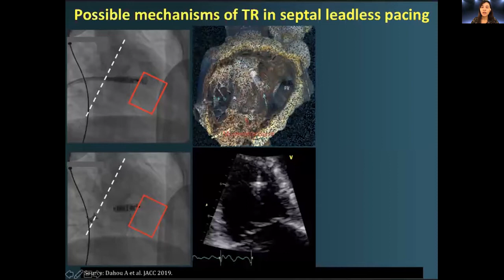As shown in the figure on the top, if the pacemaker is positioned with the tip just lying in the mid-septum, the final position may actually be displaced a little bit to the proximal area after the catheter shaft is withdrawn. This increases the chance for the leadless pacemaker to entangle the septal chordae, which are either attached to the small papillary muscles or directly to the septum. And second, the body of the leadless pacemaker has a diameter of 6.7 millimeters, which is 2.5 times the size of an ICD lead. If you leave it at the more proximal part of the septum, the device body may interfere with the valvular leaflets as well as the chordae.